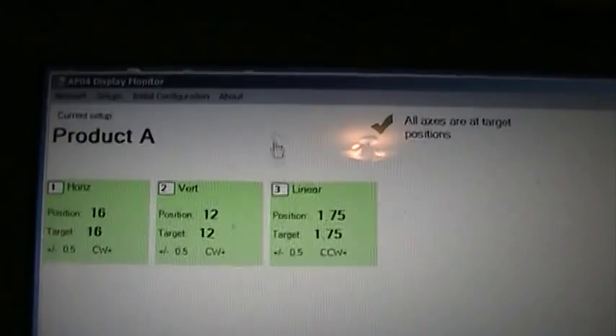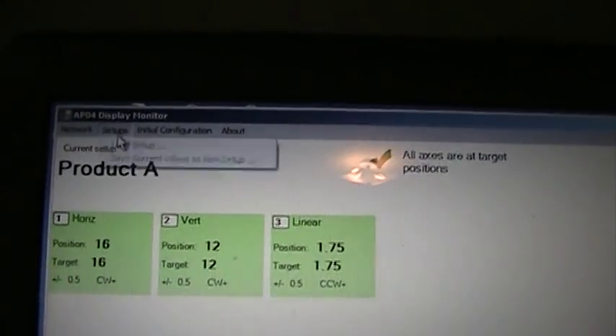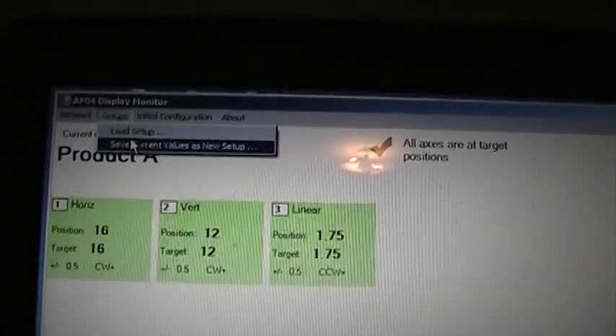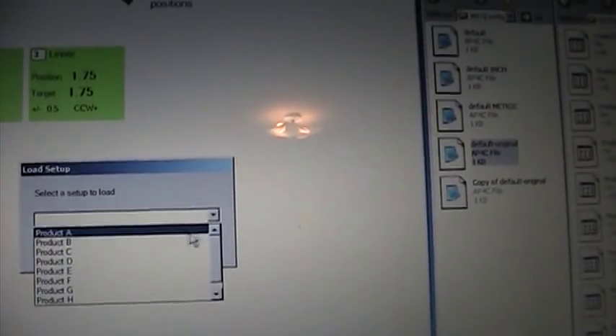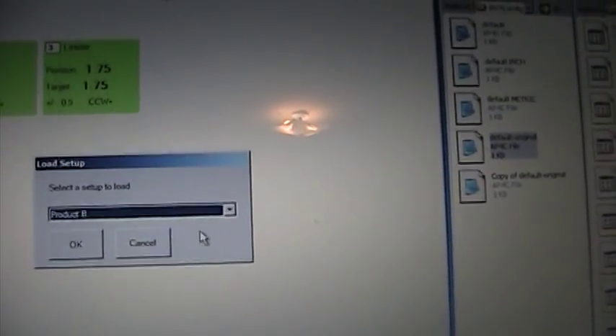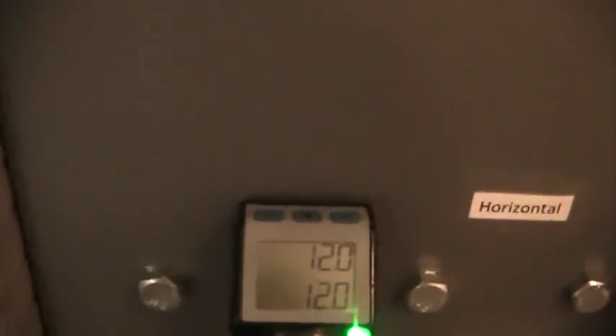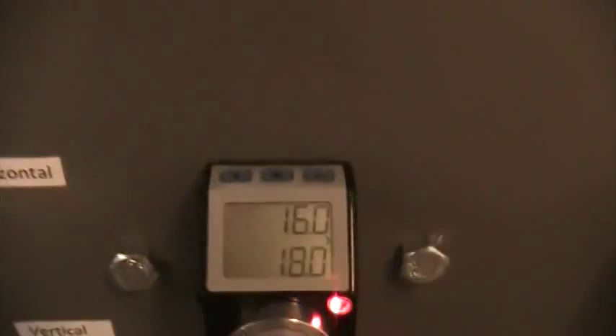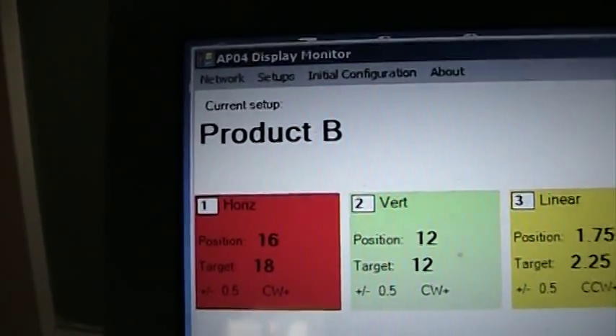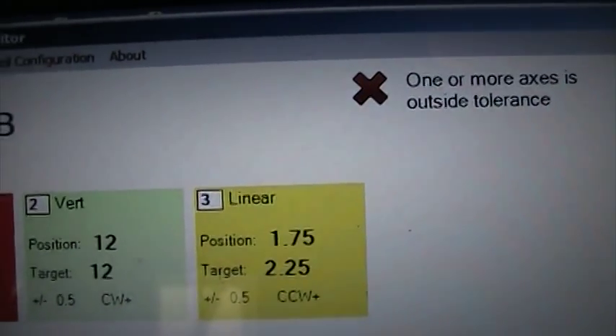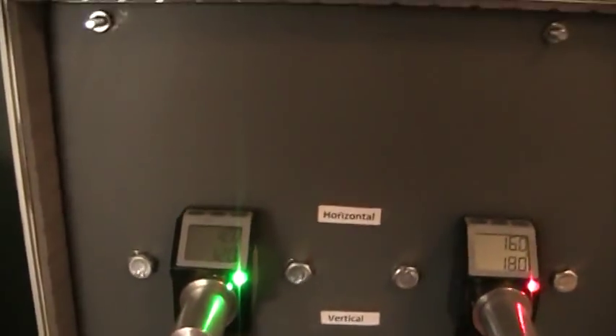Let's switch to product B, and I'm gonna go to the menu, choose a predefined setup. Now, keep in mind, I can be doing this while I'm still running product A. So I download to each adjustment point the new setup value. I have a screen that shows me which axes are out of tolerance, right on, within the tolerance, but not right on, and it's time to switch from product A to product B. I just make the numbers match.